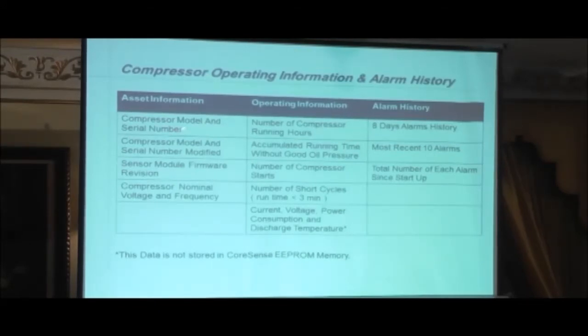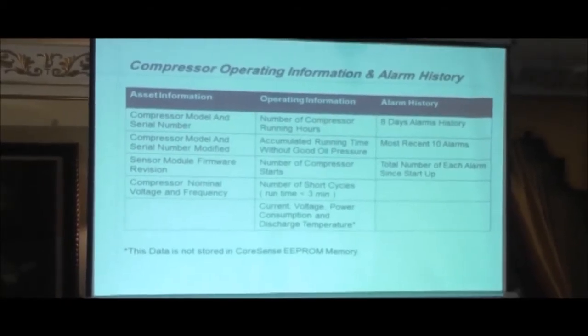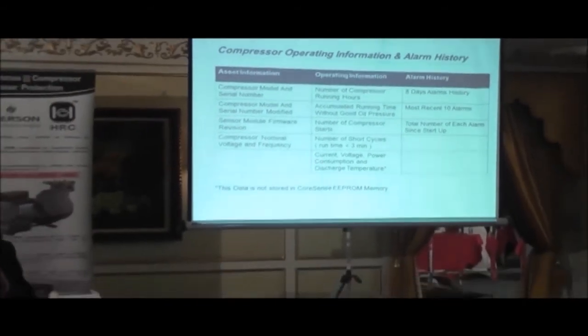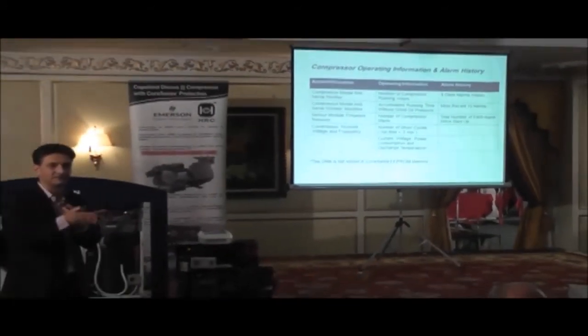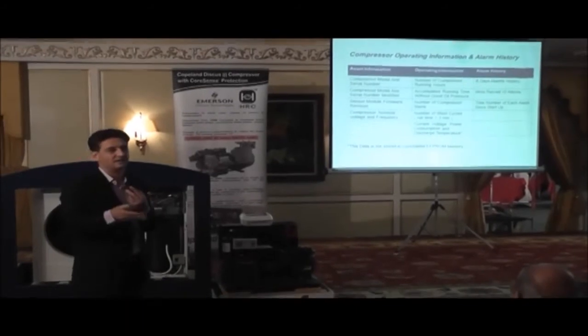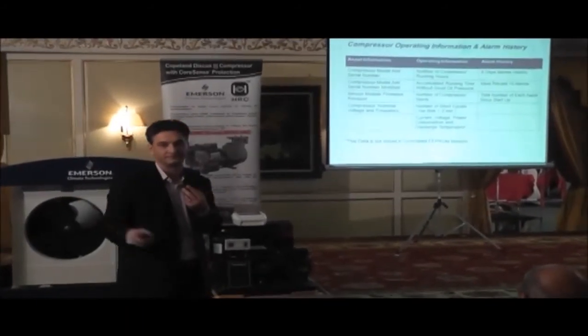This is all the information you can extract from the module. You can get the compressor model and serial number, the sensor module firmware, the compressor nominal voltage and frequency. Right? This is pre-programmed to the compressor. Operating information. You can extract the number of compressor running hours. Okay? So from the day that the compressor or condensing unit was installed, if you keep a record of that date, you know how many hours that compressor runs every single day.